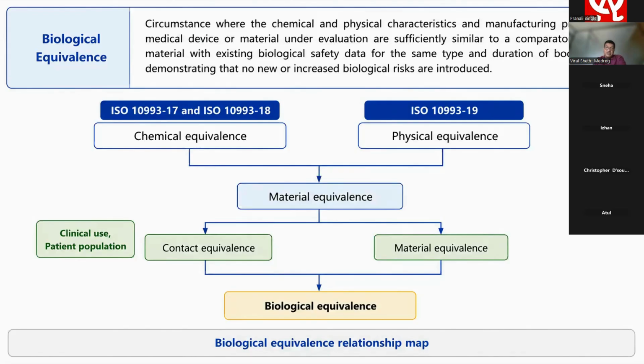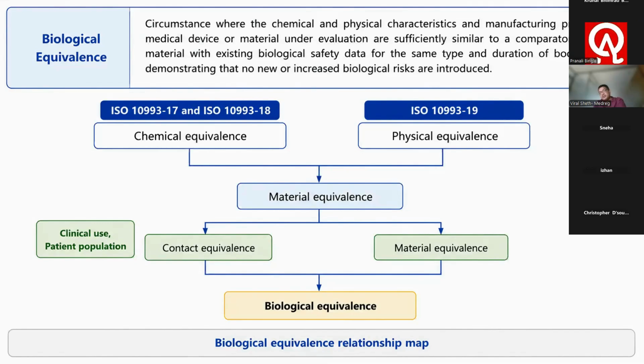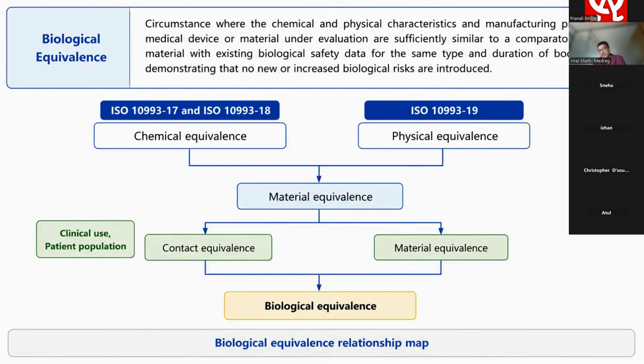Once you confirm the material equivalence by chemical and physical, you can talk about the clinical condition equivalence of your device, and everything is matching to the predicate. Predicate means a device already approved by the concerned authorities and available in the market. So you need to compare your device with the predicate depending on the interest of your regulatory authority, maybe India, Europe, US, and others. As a consultant, we understood that if you follow the structure of Europe and US and comply with all their requirements, you should indirectly comply with the requirements of other countries too, irrespective of the administrative formalities mentioned in their guidance documents. So this standard allows you to claim biological equivalence by chemical and physical characterization.